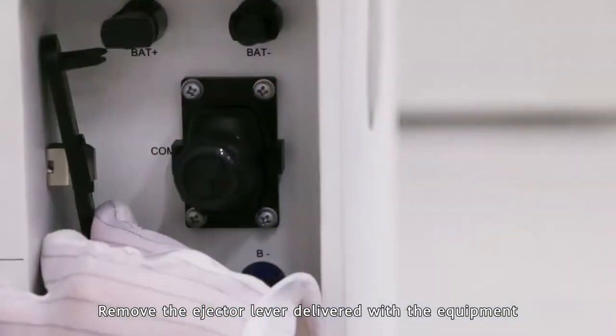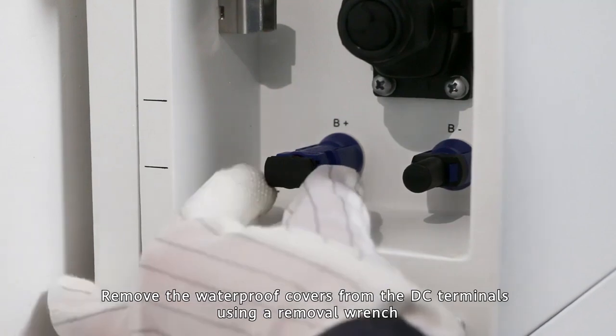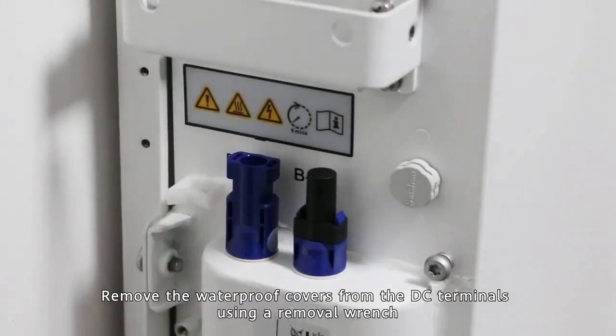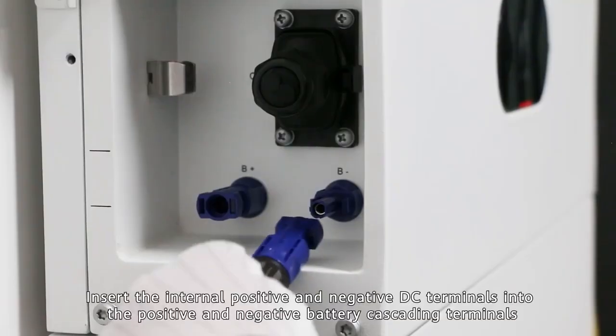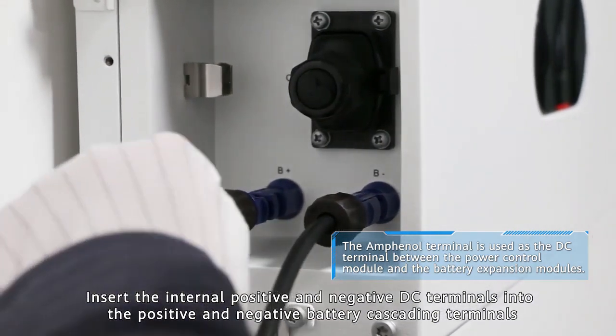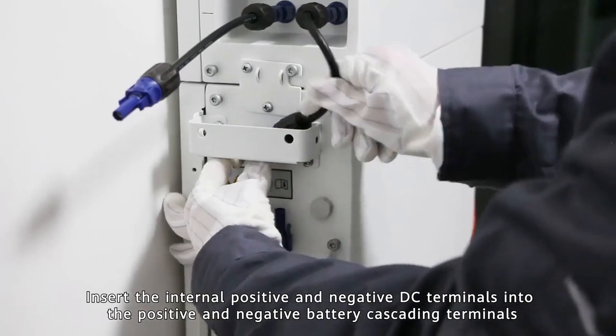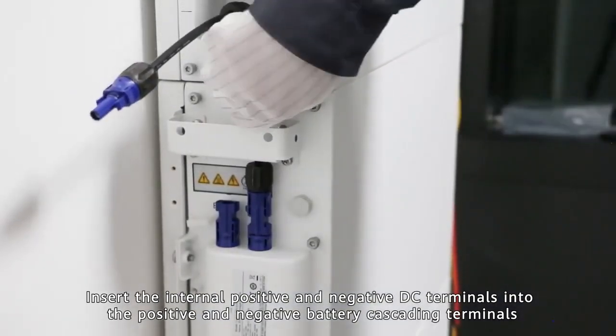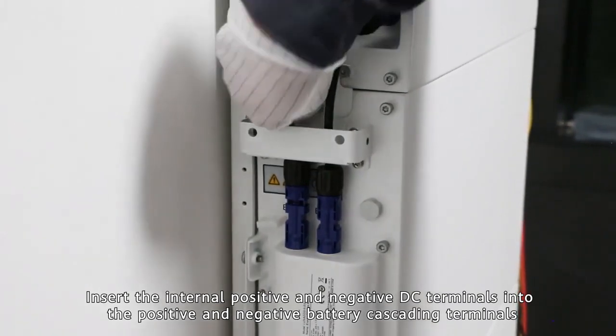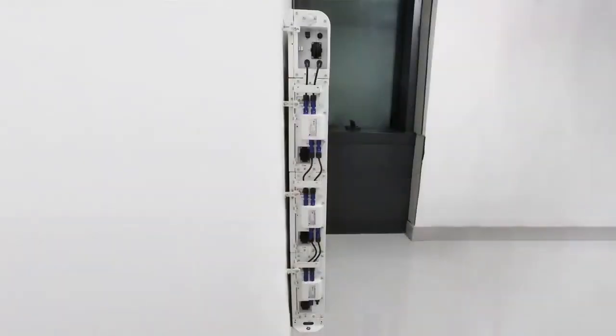Remove the ejector lever delivered with the equipment. Remove the waterproof covers from the DC terminals using a removal wrench. Insert the internal positive and negative DC connectors into the positive and negative battery cascading terminals.